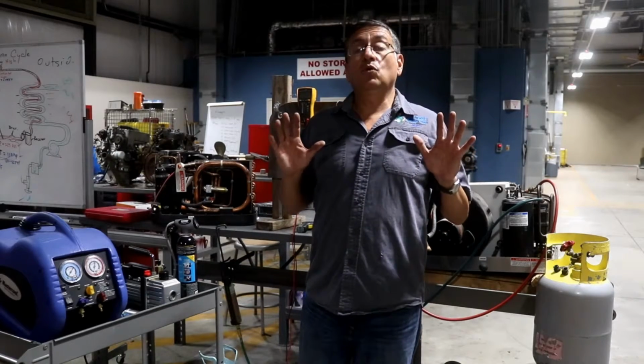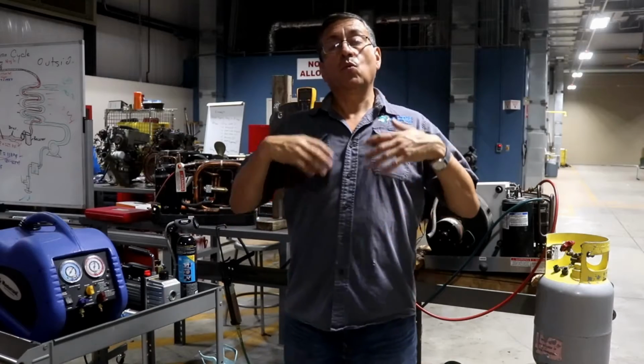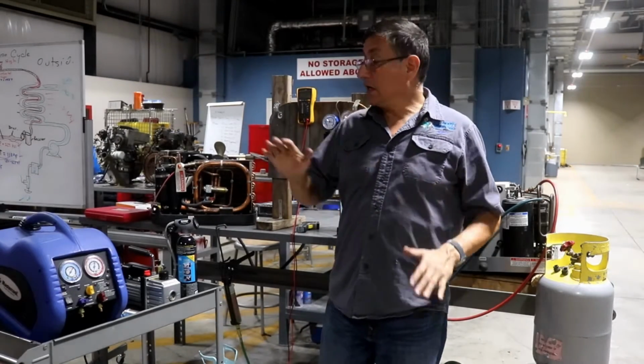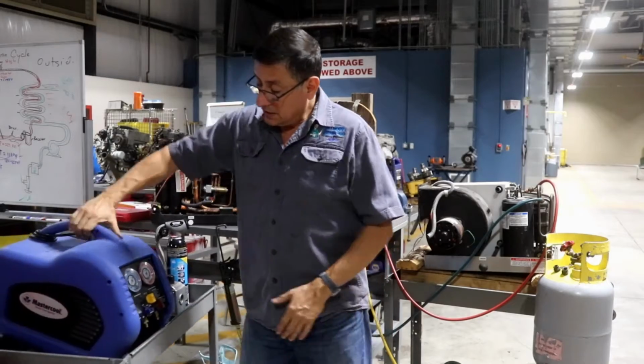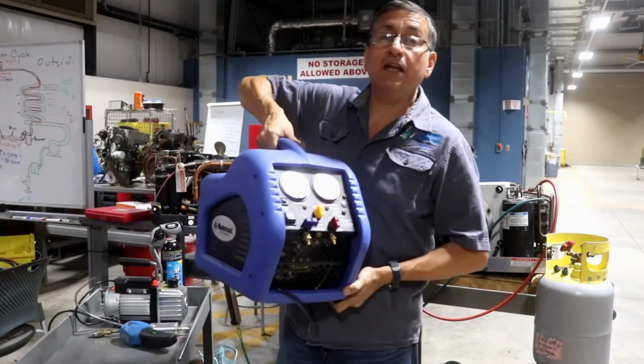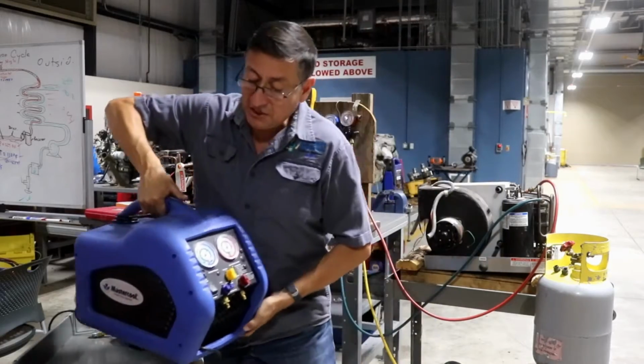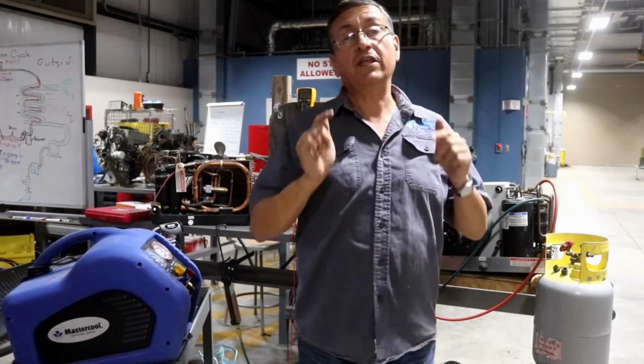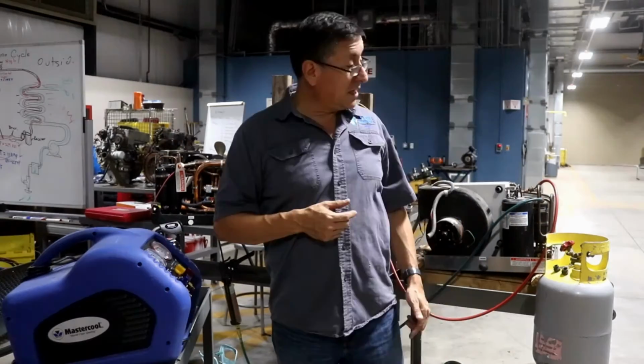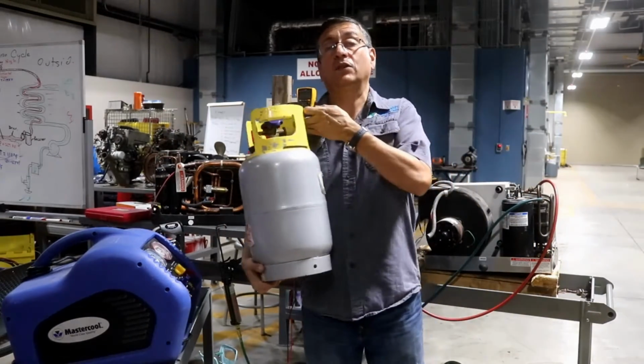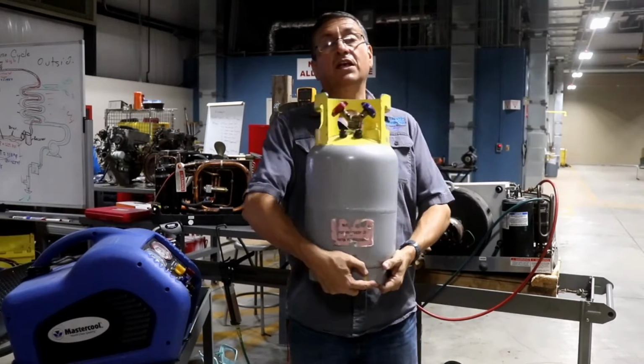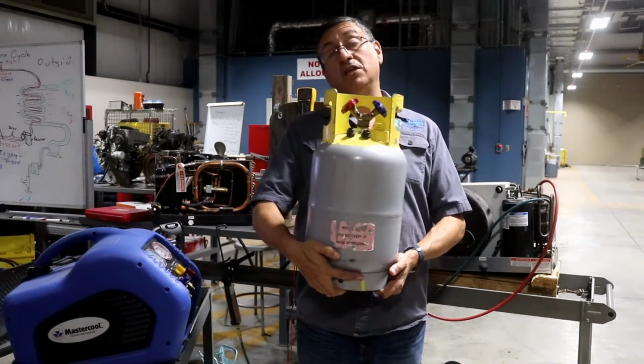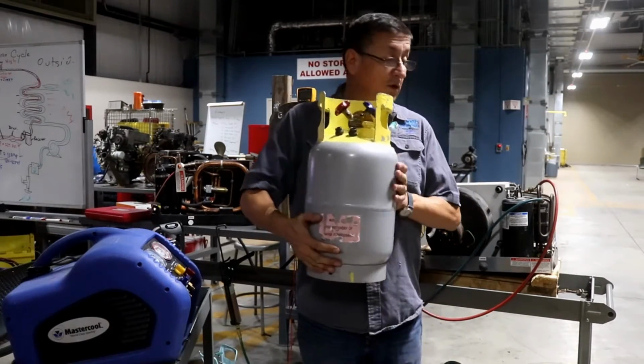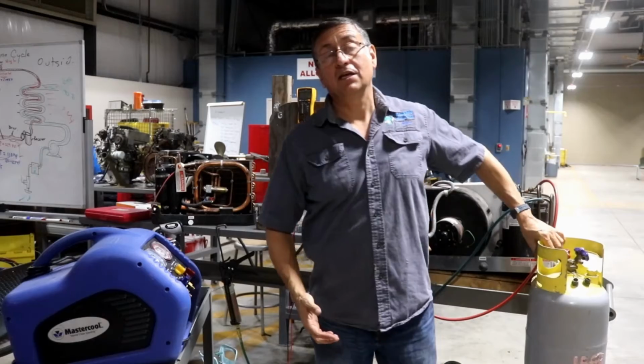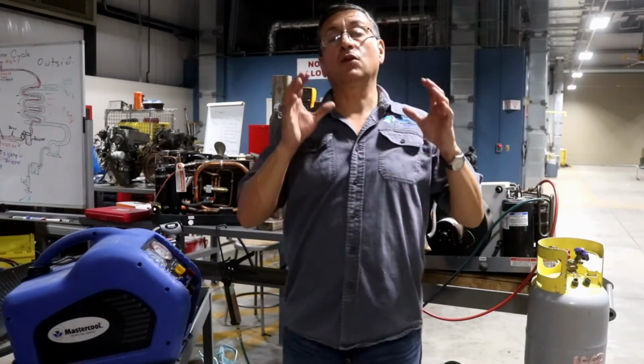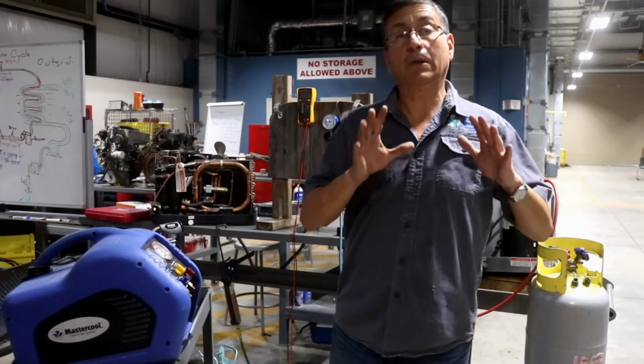In some cases, if you want to be dedicated to working with marine air conditioning equipment, I recommend trying to buy this equipment. This is the recovery equipment, the recovery machine. With this machine, you can recover the refrigerant and you can charge the refrigerant again. Of course, if you want to work in this business, you need the recovery tank. Probably you need more than one, because depending on the refrigerant used, you use one or the other in order to keep the refrigerant stored properly.